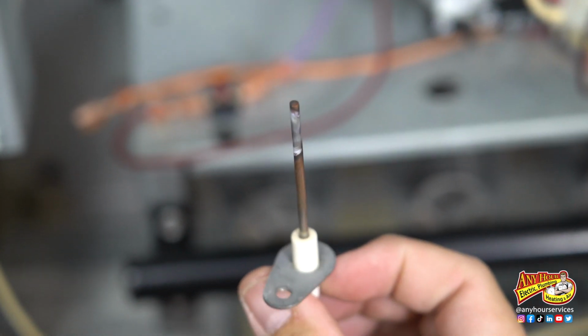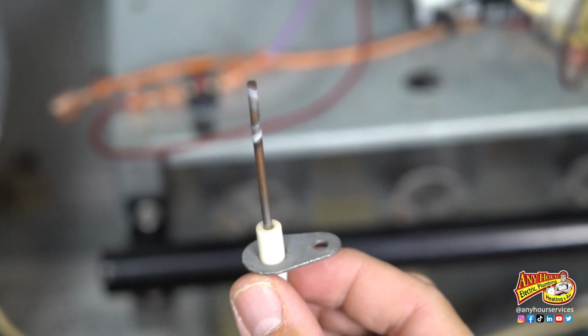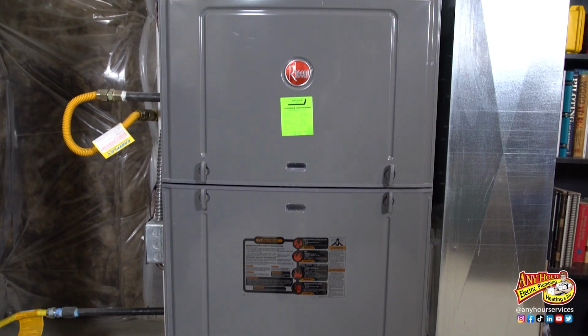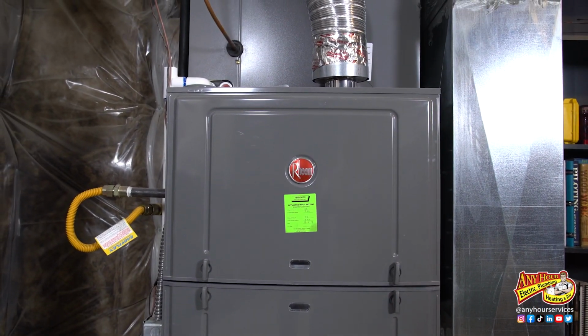Now, this can happen because of improper air to gas mixture. Maybe the gas ports haven't been adjusted properly, or maybe it was never adjusted for your altitude. That's why the gas company recommends having like a green sticker inspection where they come out and they make sure that things are done properly that way.